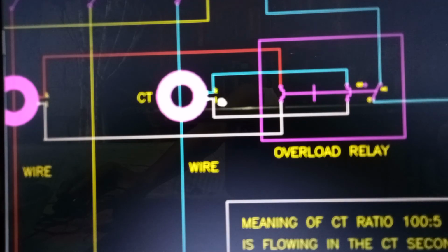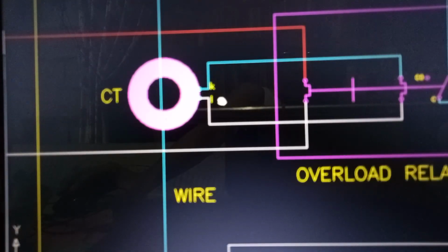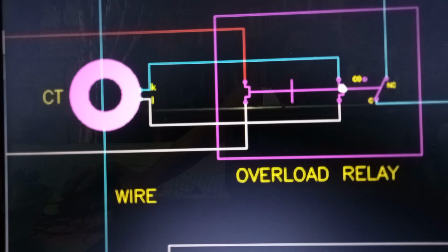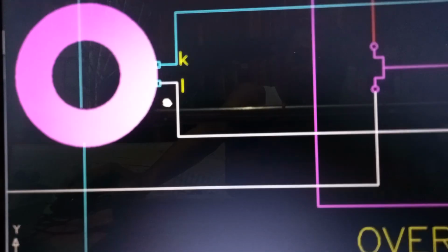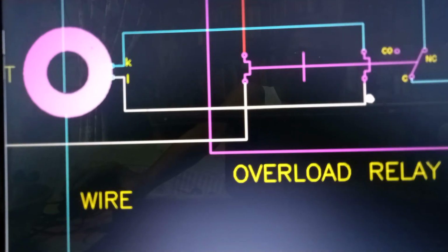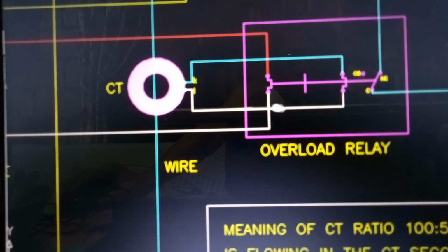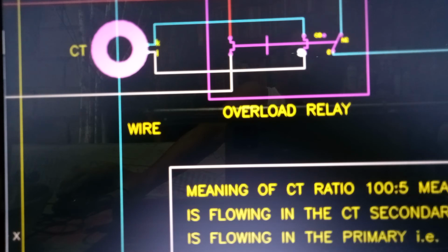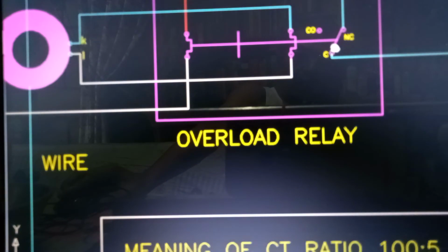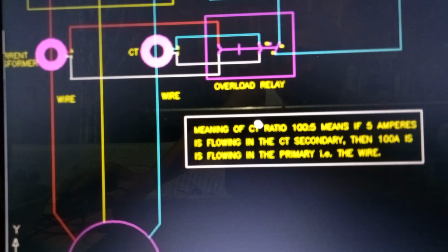Similarly, the small letter K on the CT of line 3 is connected to the heater on line 3 of the overload relay. The small letter L on the secondary of the CT is connected on the load side of the heater. So here are the normally closed and the normally open contacts of the overload relay, which are connected to the control circuit.